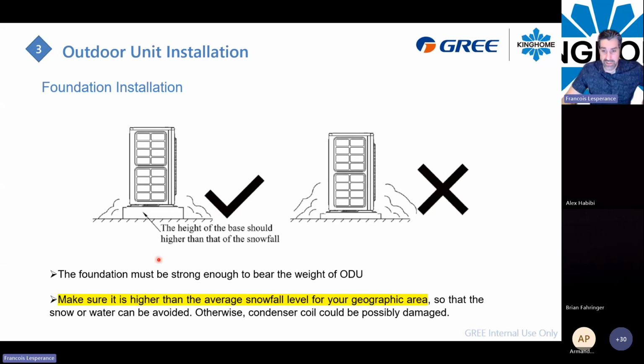So make sure you have a proper rack or a proper level for the outdoor unit. Regarding the average snowfall in your region, I know for me, I'm in Quebec, it's at least 20 inches, so I need to put this unit high enough. But in your region, if it's a little bit less than that, make sure you have the proper rack to not have an accumulation of snow building up in front or behind the unit.